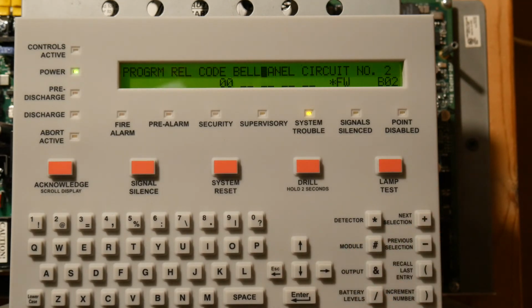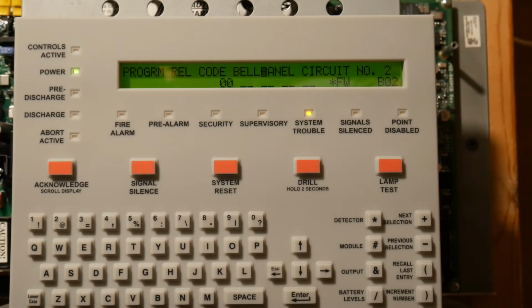Release code bell basically means it'll code the bell so that when one zone is activated, like a smoke detector, it'll do a slow march time. And then when you do a manual release, it'll do continuous. So we'll set this as agent release. And we're going to set this as agent release number, I think it was that number.